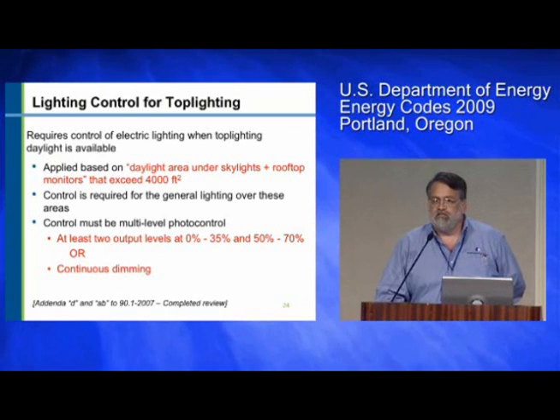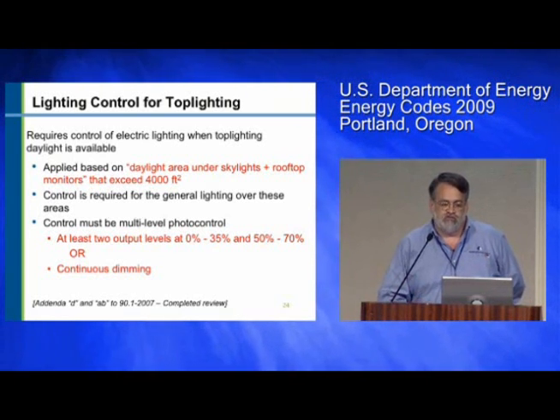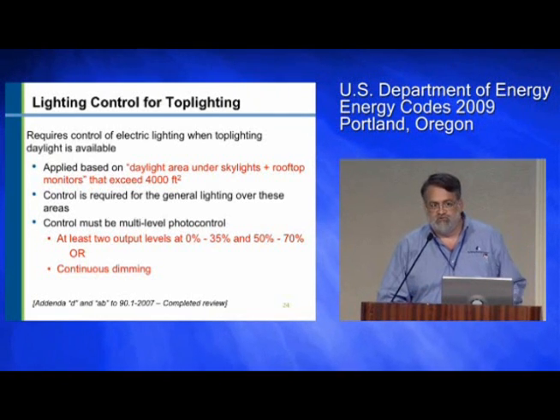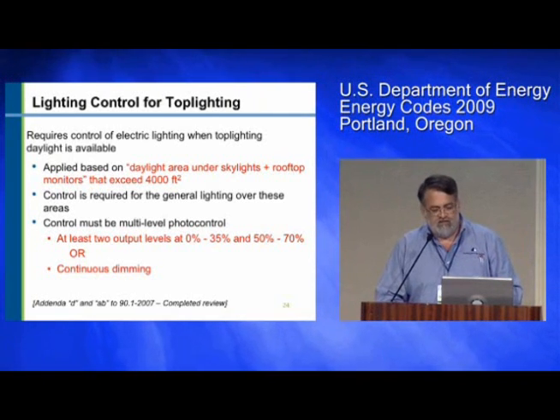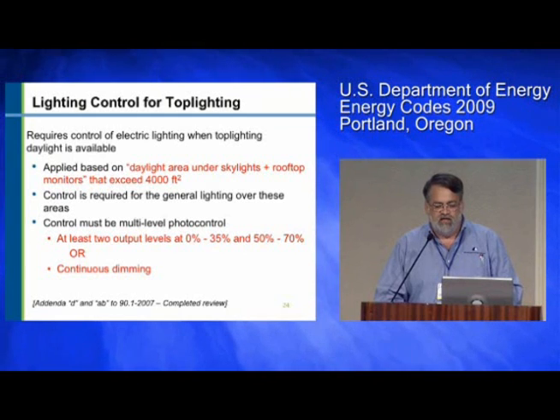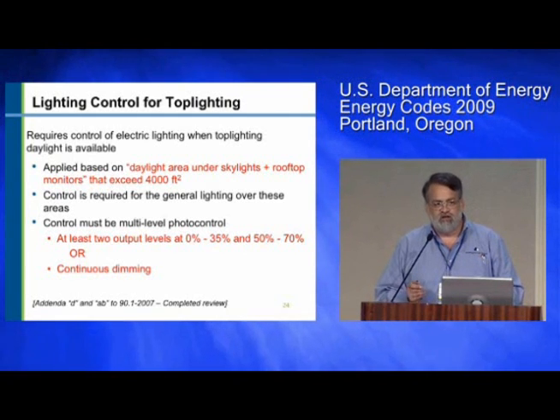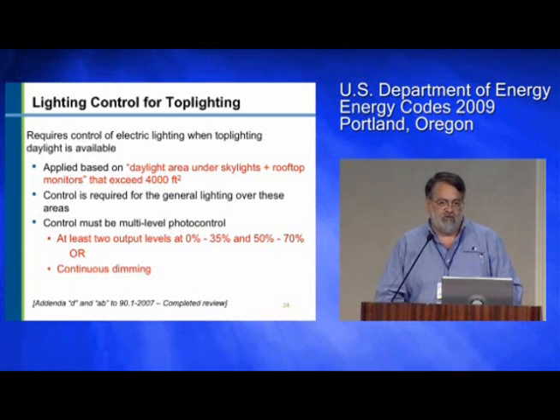It has to be at least a 2-level output. It can't be just on-off. It has to provide either 2 levels or continuous dimming. So what about the daylight area under skylights? As everyone knows, daylighting can be very complicated. It can be hard to implement. It's got issues, and that's why there hasn't been a requirement until now.